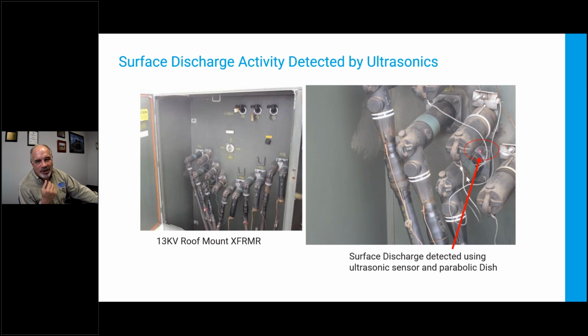What happened is the guy terminated the cable. He terminated a little bit short, but he had a crowbar so he could make it fit. And in doing so, bent the bushing, bent the rubber boot. There was an air gap. That air gap was not the same permittivity as the rubber, caused the discharge. The whole inside of that boot was covered with white powder and tracking. And they pulled a new cable, replaced it, worked fine. I went up and I tested it. It was dead quiet.